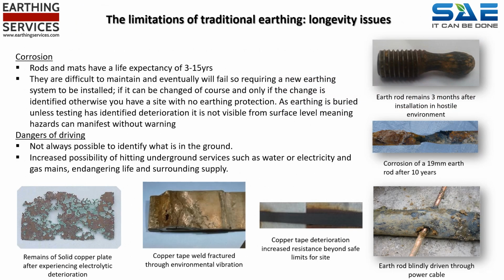Here we see evidence of copper earth plates, copper tapes, and earth rods that have deteriorated beyond usefulness. Whilst not shown, a lattice is not as substantial as a copper mat, and so would fail even more significantly by comparison to the same faults and environments. The earth rod we see here that has been blindly driven through a power cable resulted in the hospitalisation of a worker and financial penalties, along with the RIDDOR incident report.